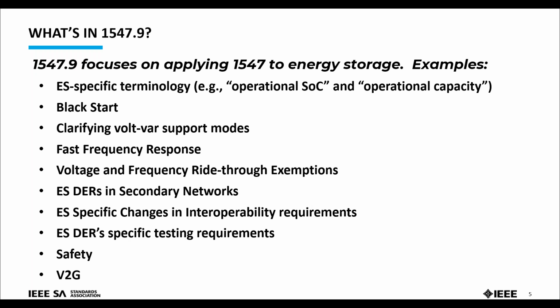Some of the rest of these items are fairly typical for energy storage, like fast frequency response. It's difficult to work with fast frequency response when energy storage is on the distribution system, because that system just isn't designed to support it—this limits how much active power we can get out of that part of the system and how quickly. So 1547.9 gives some guidance on how all of that works.